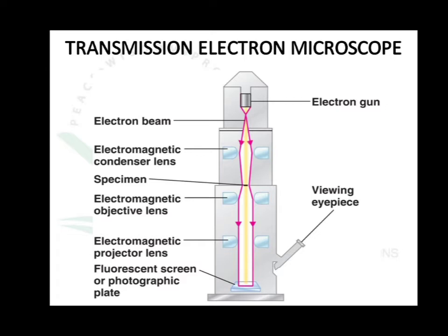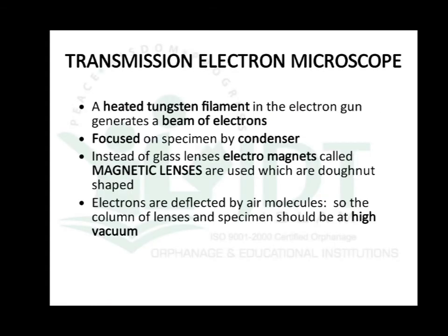We cannot observe the image directly with the naked eye because we are using an electron beam as the source. Also, the electron beam can be deflected in air, so all parts of the electron microscope must be maintained under high vacuum. In summary, we have a heated tungsten filament, condenser and electromagnetic lenses, all kept in high vacuum.